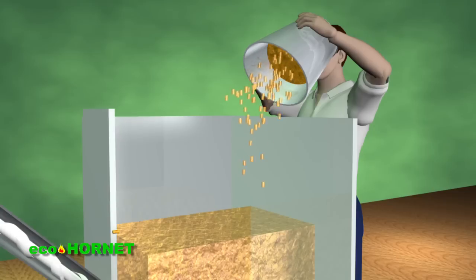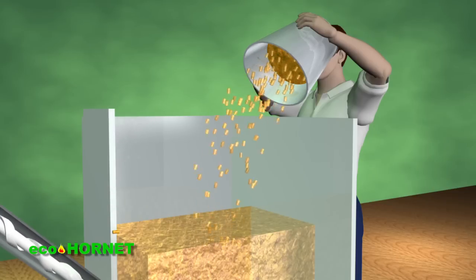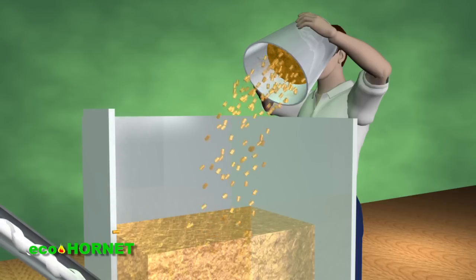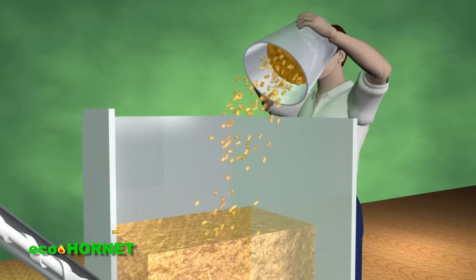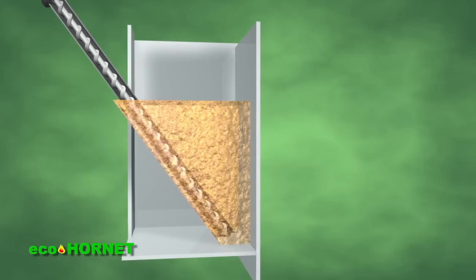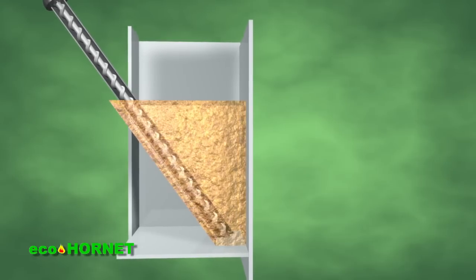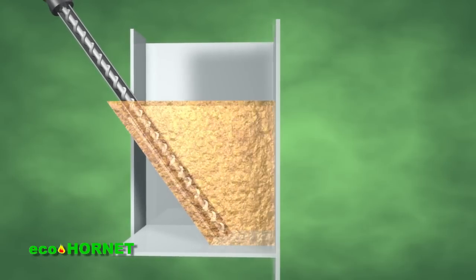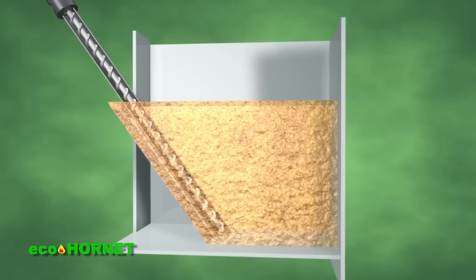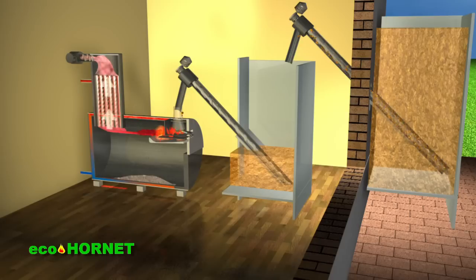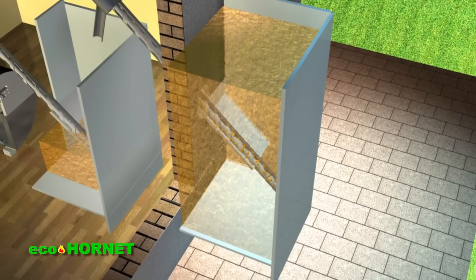The pellets used for fuel fit into a bunker whose capacity ensures the operation of the heating system for a minimum of 48 hours at maximum power. Depending on the available space, the bunker's capacity can be increased for a significant increase in operating autonomy. The bunker of the heating system can be connected to a high-capacity tank, located outside the area of the heating system. In this case, the feeding of pellets can be mechanized.